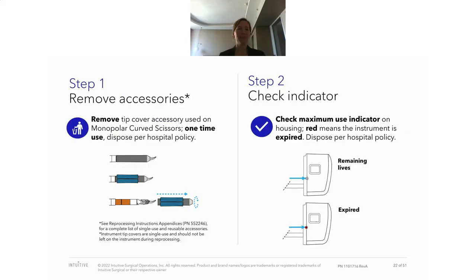So let's start with the first step. Again, removing the accessories. In case you still find some, for example, here the sheaths still on the instruments, it's really important to have that step to double check that it is actually removed before you start the cleaning process, because if it is still left on there, the cleaning will not happen in the right way and it will have to be redone. Second step to double check: is the indicator red or still white, so that you can avoid reprocessing something where there's no need.